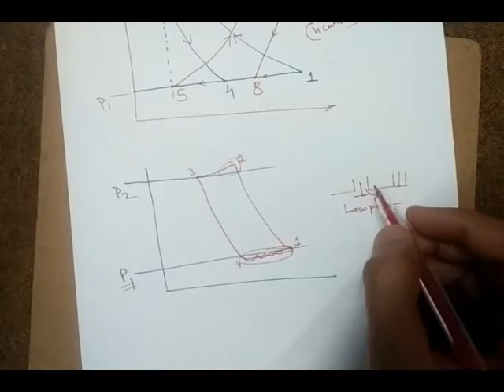It will come back to the original pressure, but to start with, to initiate the valve opening, the compressor should go to a little lower pressure, so that inside this chamber the pressure will be a little lower than the suction pressure. At that time the valve will get opened. That means exactly at P1 the valve might not open, so there is a necessity of extra low pressure. So some work is done on the valve also to open it, then the atmospheric air enters. So exactly at 1 bar pressure the valve might not open.